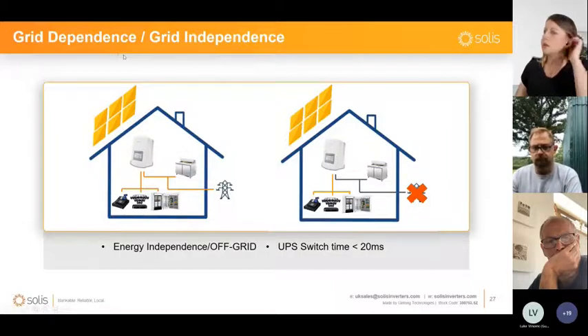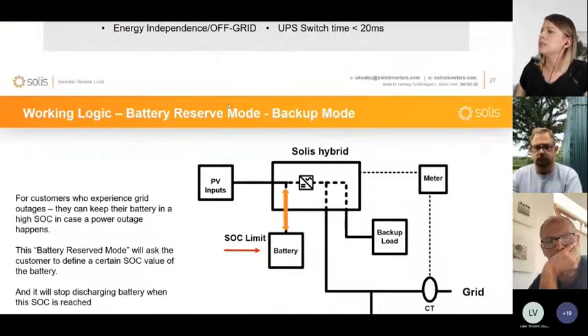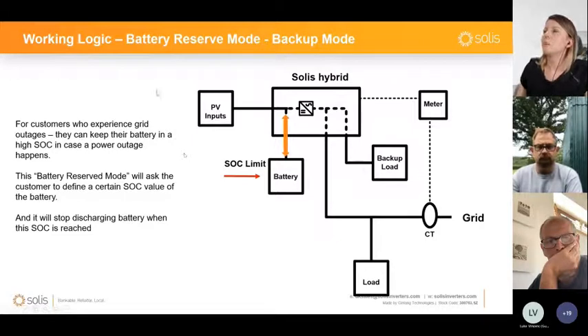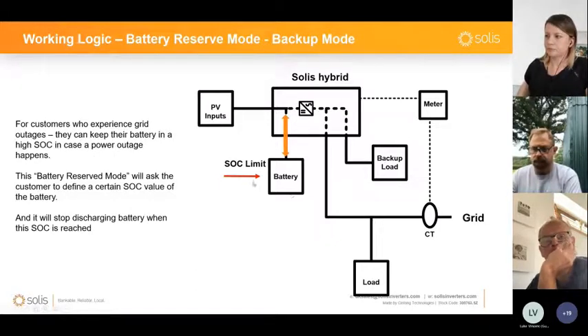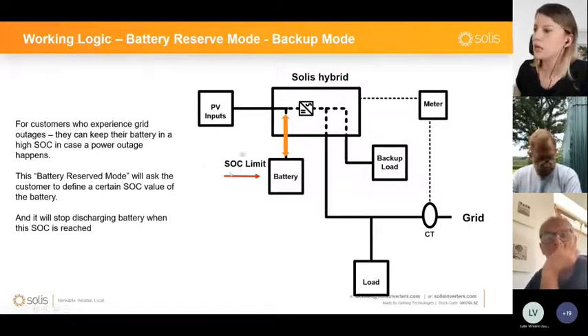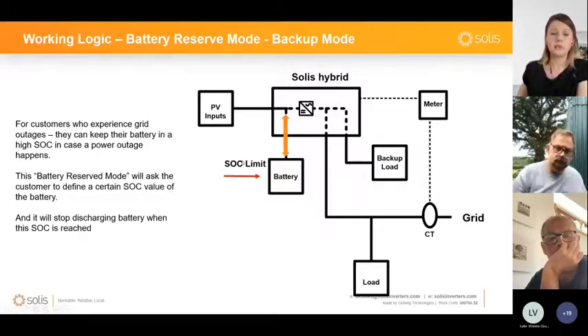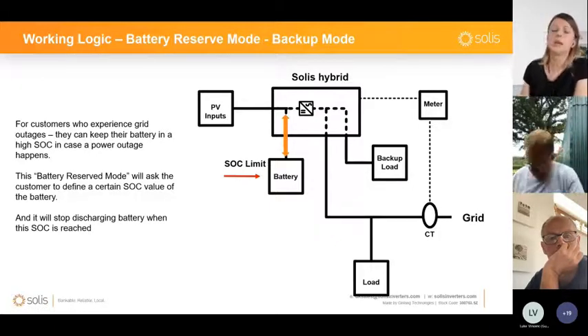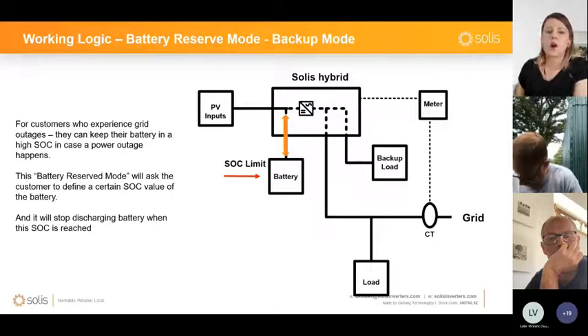So when it comes to grid independence, we have the battery reserve mode, or the backup mode, as I mentioned, where the customer can set up an SOC limit. SOC, I don't know if I mentioned, maybe not everyone is familiar with the term. That's the state of charge of the battery. That's going to tell you how much energy is still available in the battery, and that's always in percentages. So when the battery is full, you're going to have a 100% SOC.